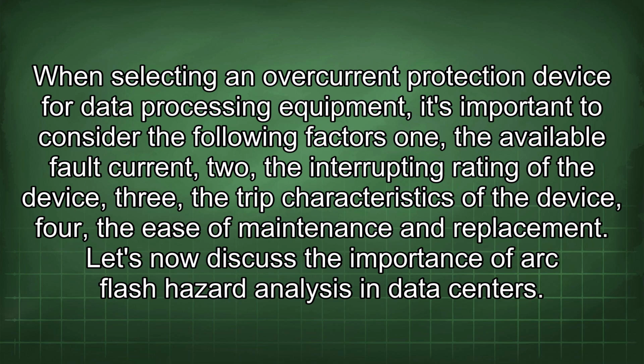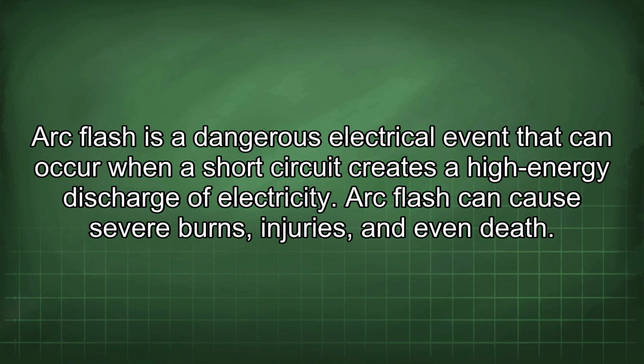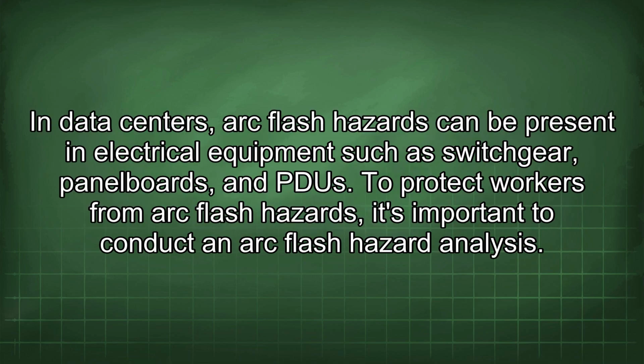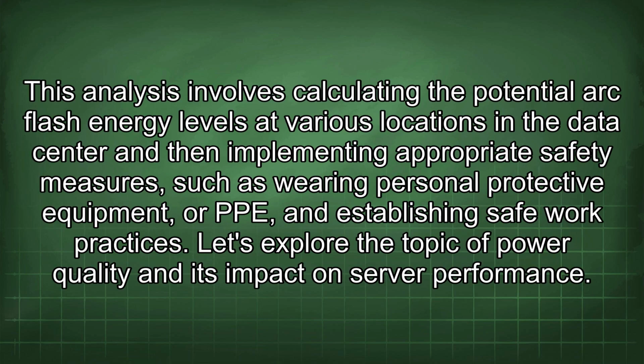Let's now discuss the importance of arc flash hazard analysis in data centers. Arc flash is a dangerous electrical event that can occur when a short circuit creates a high energy discharge of electricity. Arc flash can cause severe burns, injuries, and even death. In data centers, arc flash hazards can be present in electrical equipment such as switchgear, panel boards, and PDU. To protect workers from arc flash hazards, it's important to conduct an arc flash hazard analysis. This analysis involves calculating the potential arc flash energy levels at various locations in the data center and then implementing appropriate safety measures such as wearing personal protective equipment, or PPE, and establishing safe work practices.